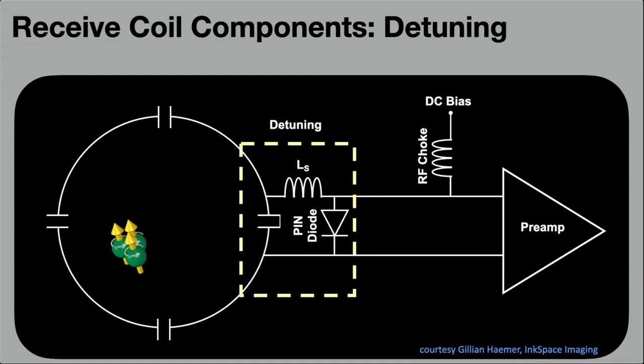But what if this doesn't work? That's a single means to reduce risk—well, what if it doesn't work? And when does it actually not work? Well, what if the coil is not connected? Somebody forgot to connect the coil, so now the DC bias cannot go and turn on that PIN diode. Now you've got yourself a resonant coil sitting on a patient without it being connected, and the system doesn't really alarm anything. It can introduce very high current and actually endanger the subject or the patient.